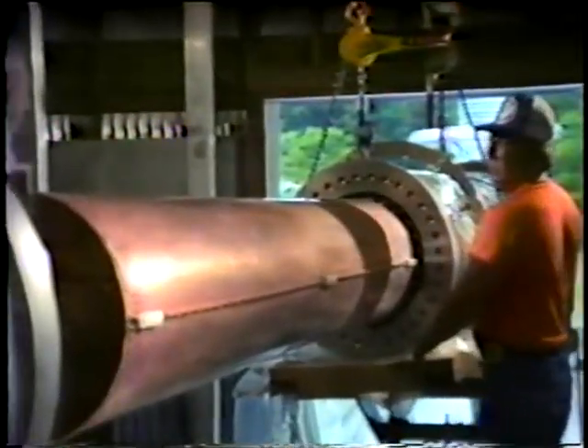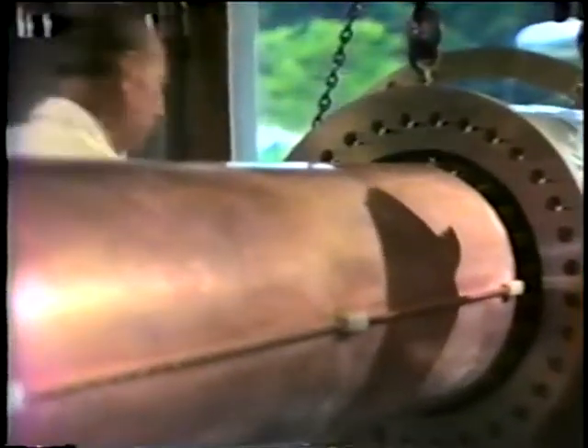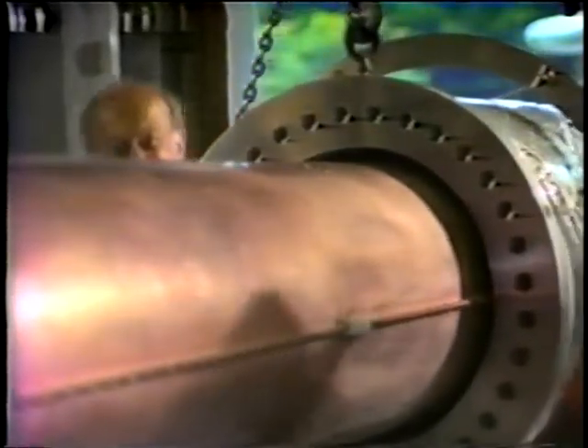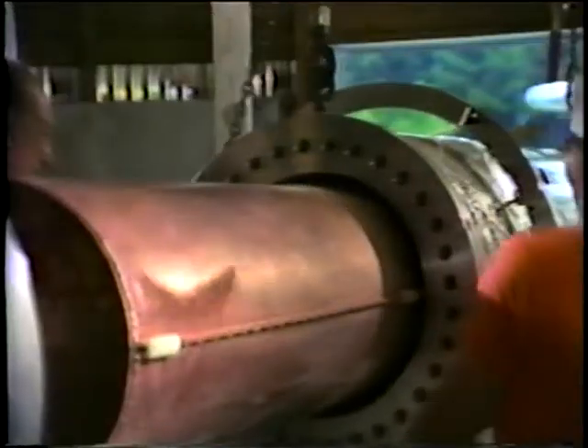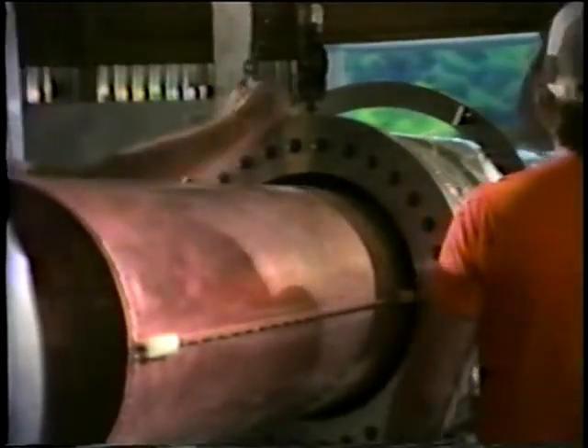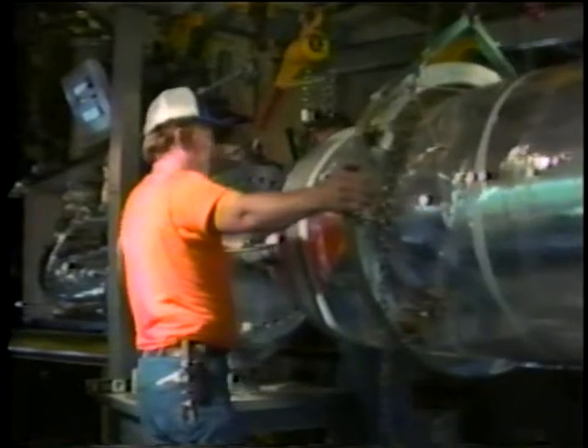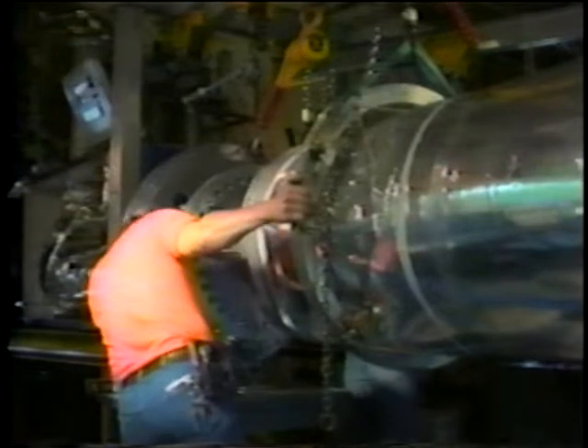When the electrical connections are completed, a large cylinder slides over the assembly, which contains the high-pressure helium gas used to cool both the cables and the terminations. The cold helium gas from the refrigerator is introduced into the system at the west terminations. Most of the gas flows to the east end, but a small percentage is used to cool the termination conductors.